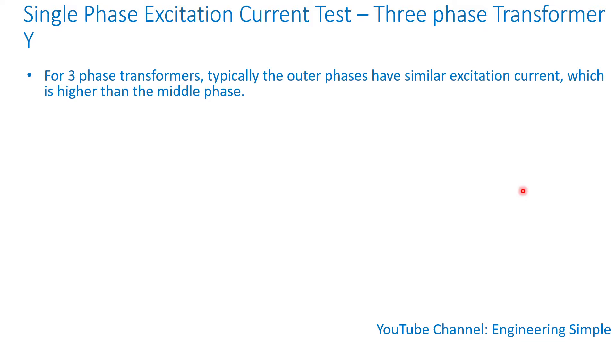For single phase excitation current test performed on three phase transformers connected as a Y, typically the outer phases have similar excitation current.